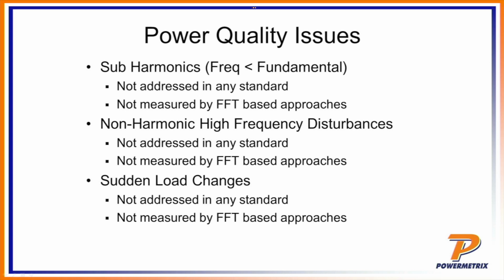Last thing that we're going to talk about is some other power quality issues that we've not really touched on today. Another issue that we see nowadays is called subharmonics. Subharmonics would be harmonic energy that is actually less than the fundamental. Rather than being 60, 120, 180, it would be, say, 30 hertz or 15 hertz. These are not being addressed in any standard right now. They're not being measured by any sort of FFT-based approach.